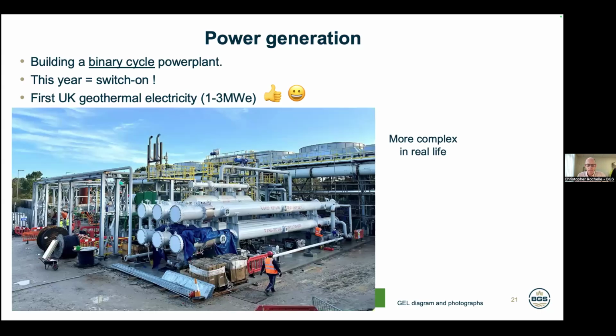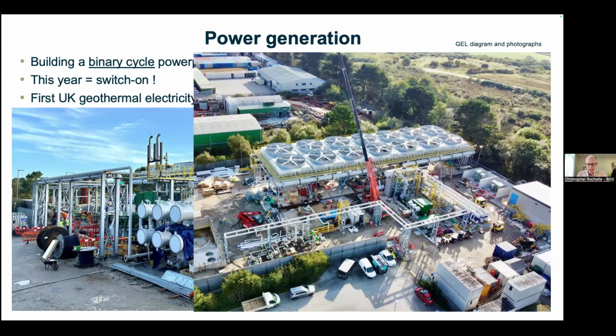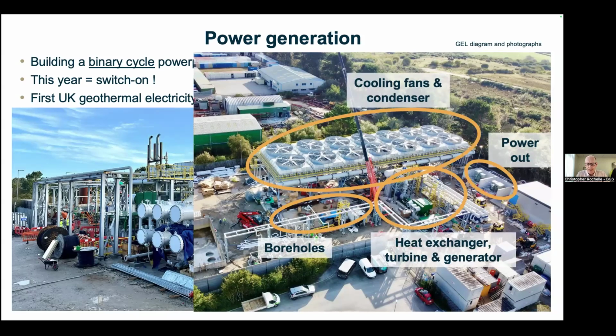It's more complex in terms of plumbing in real life, and an aerial image shows that. You've got a range of different things amongst all that pipe work. In the middle of it all, hardly visible, are the 2 big boreholes. They feed the hot water to heat exchangers with a turbine and generator in the middle - that's the part in green. On the right-hand side are 2 little transformers to send the power out to a power line next door. At the back, what's really more visible is the cooling fans, a condenser to recondense the organic fluid back into liquid form to send back through the system. So it's quite a compact site in the middle of this industrial estate.